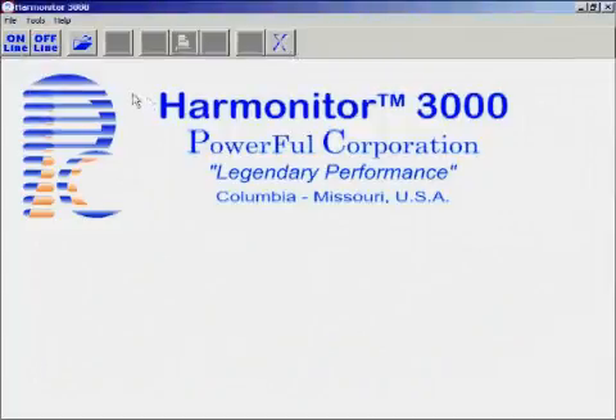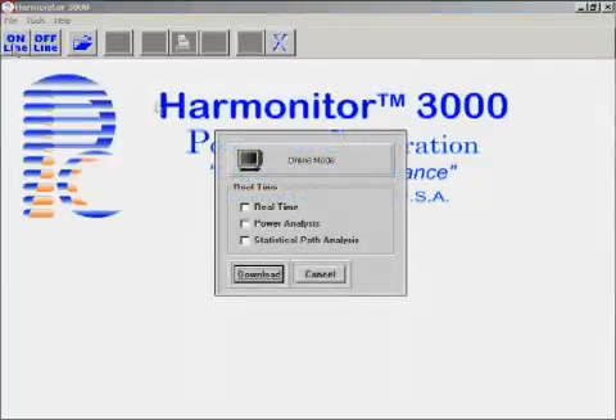To perform online measurements with the Harmonitor connected to a computer while it is connected to a load, click the Online button. This will bring up the Online Mode window. Here, you have the choice to perform a combination of real-time measurements, power analysis, and statistical path analysis. Real-time measurements allow you to see continual snapshots of the load, downloaded in real time. However, real-time measurements alone are not saved on the computer. Power analysis files, however, will show you similar information as real-time measurements, but all the data will be saved to the computer for later viewing and analysis, as we have previously covered. Statistical path analysis is a specialized tool for evaluating the performance of any electrical or energy device. For more information, please refer to the manual.